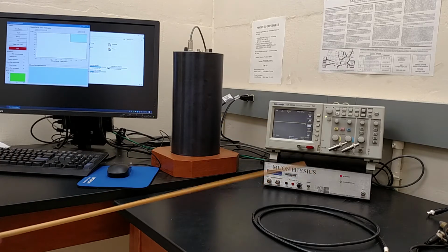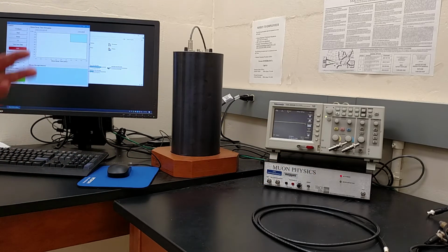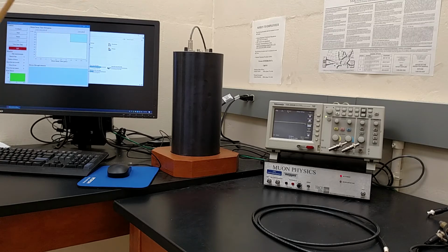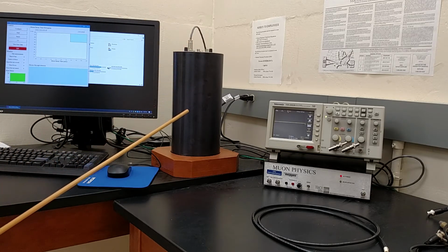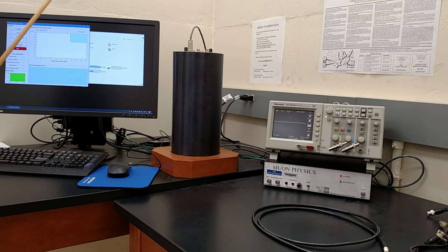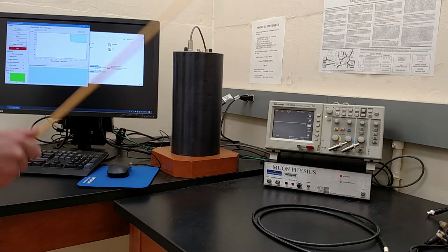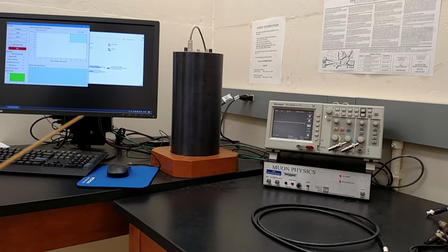Then in the electronics box we have essentially three components: an amplifier, a discriminator, and an FPGA. First the signal of the PMT is amplified by the amplifier, and then it goes to a discriminator that sets the timing for the signal, and then it goes to an FPGA, a field programmable gate array. It's an electronic component that does a variety of functions. In this case, it's programmed to do the timing and communicate with the PC for the data.